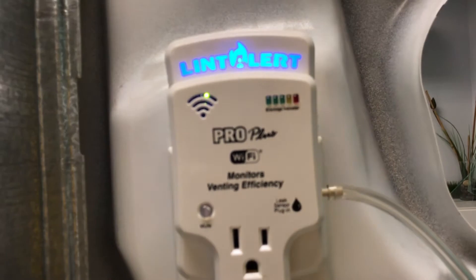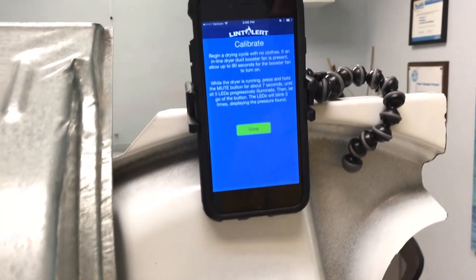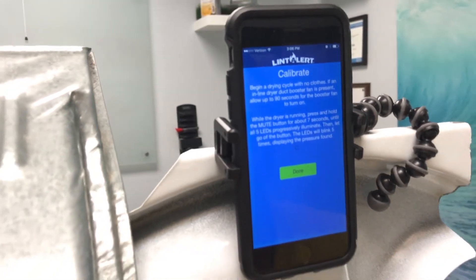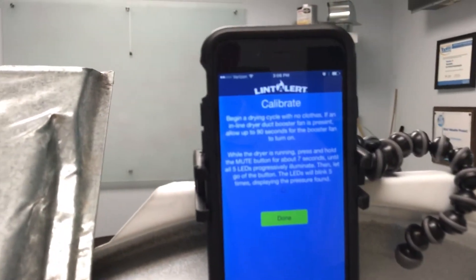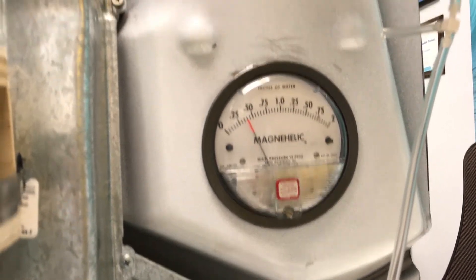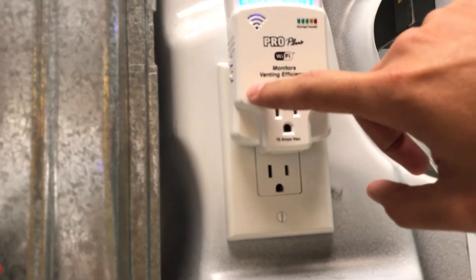The device itself — our app is asking us now to calibrate the LintAlert itself. So pardon the noise, we're actually going to turn the dryer on. Now we can see some added pressure in our system. We have about 0.40 water column inches of pressure, and I'm going to go ahead and calibrate our LintAlert — 0.40 water column inches.